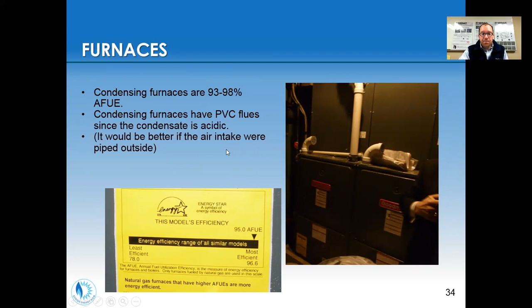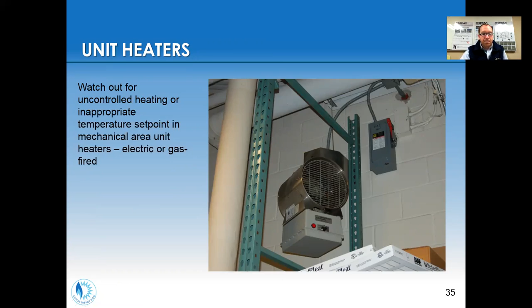We mentioned unit heaters and vestibules. They can also be in mechanical spaces, sometimes in exterior wall situations where there might be some storage, and those can be cold rooms. And the question is, maybe they should be cold rooms as long as they're not getting below freezing. So really experimenting and setting the set point on these to be as minimal as possible in those spaces can help save a lot of electric energy. Electric heat is a very expensive way to heat a building.